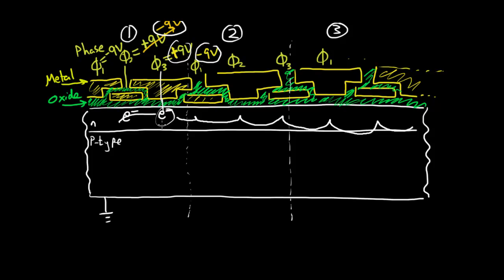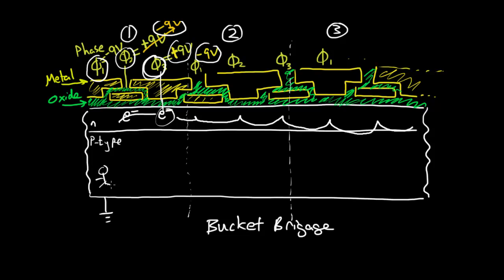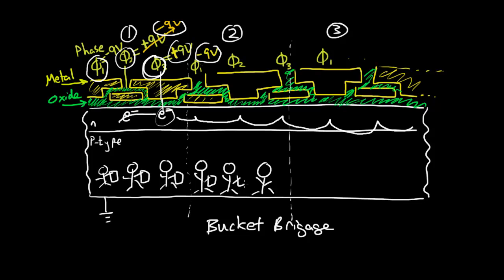An analogy that often gets drawn for the CCD is the bucket brigade analogy. You can imagine each clock phase — phase one, phase two, phase three — in each pixel being a different person with a bucket. Each pixel has three people each with a bucket, and they take turns pouring their contents into the next person's bucket until all of the water, or electrons, are collected and read out. The metal clock lines are separated from the underlying silicon by silicon dioxide, so there's no DC connection between the silicon and the metal.